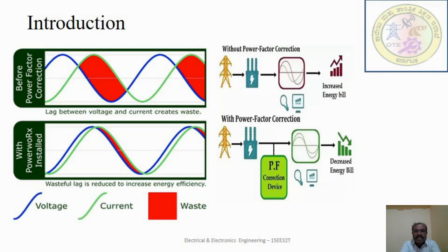In an electrical power system, a load with a low power factor draws more current than a load with a higher power factor for the same amount of useful power transferred. The higher current increases the energy lost in the distribution system and requires larger wire and other equipment. Because of the cost of larger equipment and wasted energy, utilities usually charge a higher cost to industrial or commercial consumers with a low power factor.